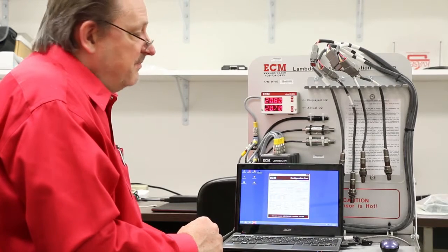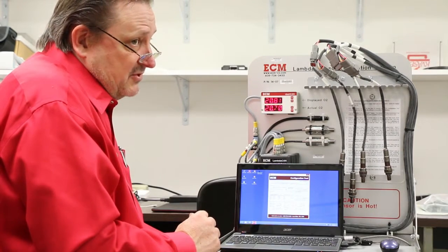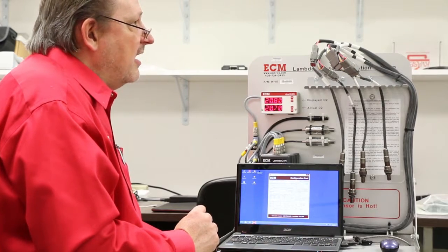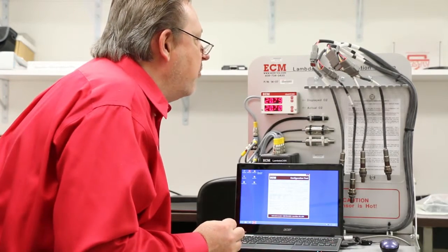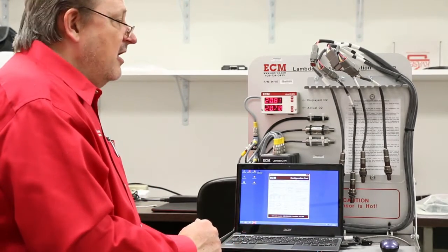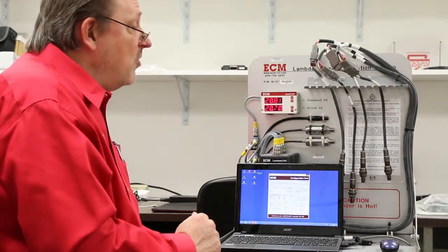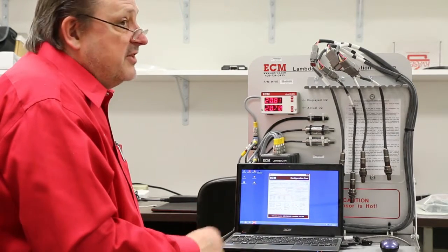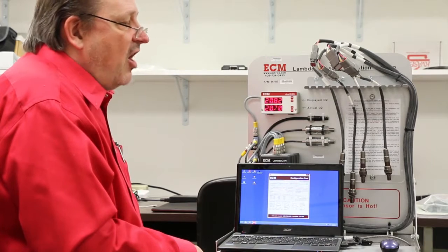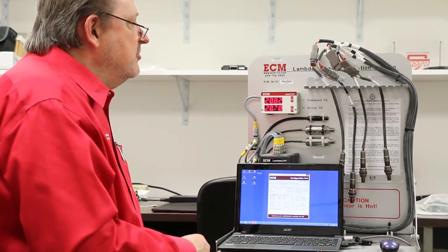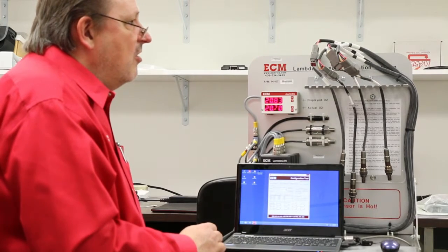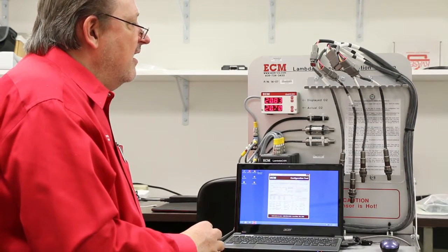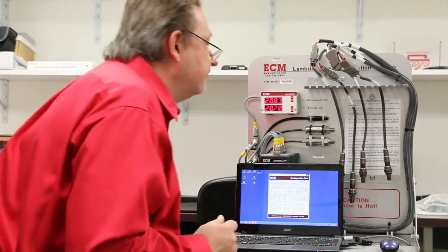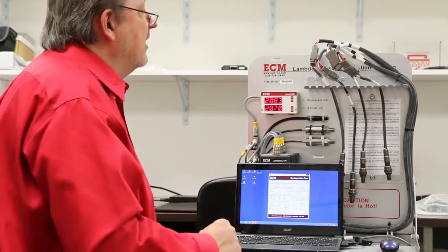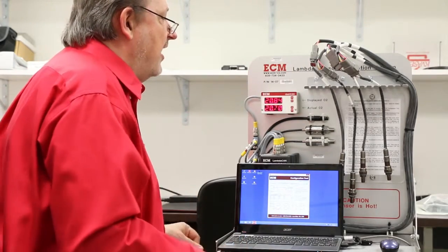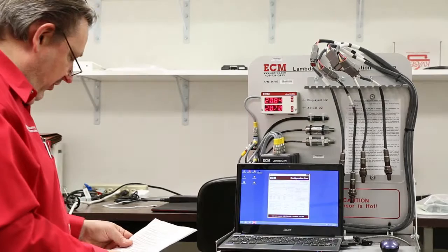When the sensor cracks, it won't give an error code sometimes, and it'll show an age factor of 1.1, which means the signal's 10% higher. This is a common failure mode when the sensor cracks. So that sensor definitely gets tossed. So if you do a calibration and you see the age factor is below 0.8 or above 1.1, throw the sensor out. Now you're finished. What you can do is disconnect the sensors, they're still hot, and distribute them for use.